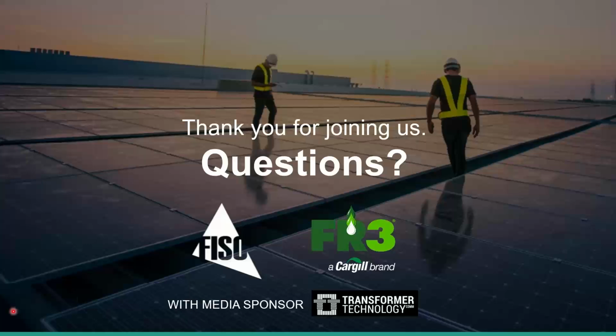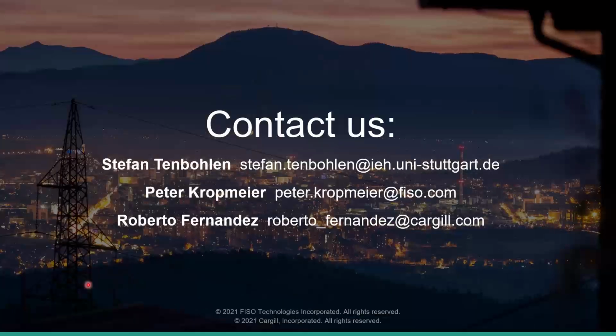The first point here is that the pour point does not reflect the actual behavior of the transformer working in the field. It's a test lab condition that is not reflecting the real conditions. And yes, we have a lot of references in northern Canada, northern Sweden and Scandinavian countries with very, very low temperatures, starting and working without any kind of problem. And I think we are out of time.